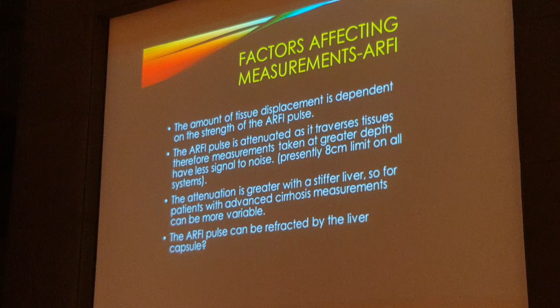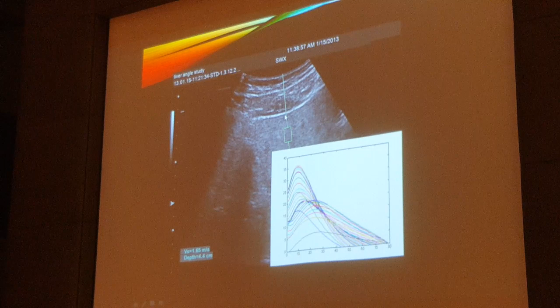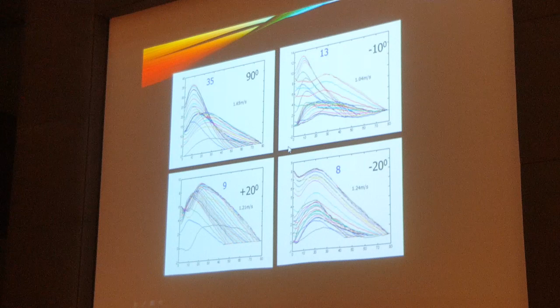And again, we did some work that I'm in the process of writing up. Here's that nice family of curves that we use to calculate the shear wave speed. You can see I put this, what I believe is perpendicular to the transducer. But if we angle the probe, and this 35 units was the peak of the shear wave, the maximum shear wave we saw when we did things correctly. If we just angled the probe by 10 degrees, that maximum was 13. So we lost more than half of the shear waves by just angling the probe by 10 degrees. And if we did it by 20 degrees, we're now down to almost a quarter of the energy. And you can see that we don't have the nice curves that we had here. They become very distorted, and you can see the measurements vary drastically. So it's very critical that you keep the transducer perpendicular to the liver capsule.